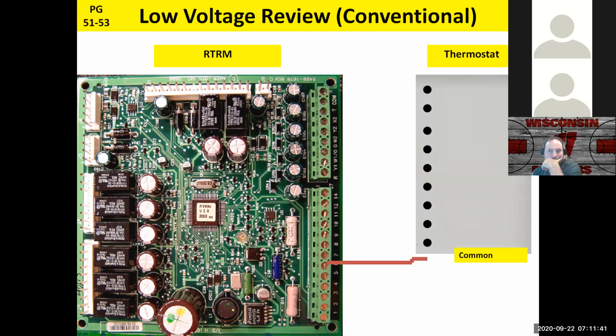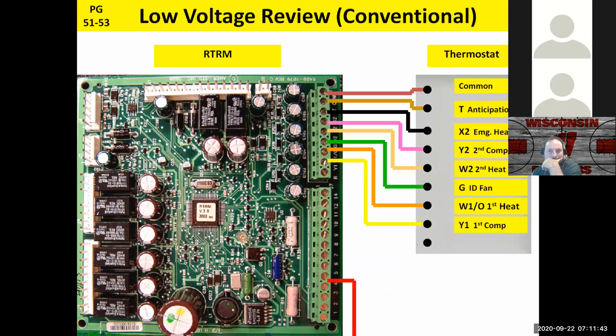And of course, that's just standard wiring connection. So you can use any good quality thermostat, R to Y1, Y2, W1, W2, G. It's pretty standard. If you have a heat pump, you may have an emergency heat situation, but it's pretty standard connections when you get to the 24 volt.